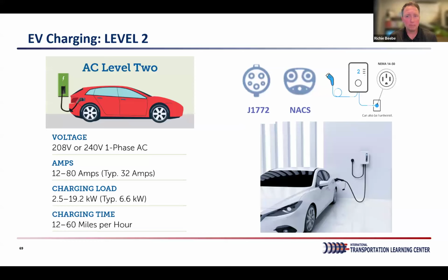So level 2 charging, you'll see this at residential facilities. It's a little bit faster of a charge. You can get anywhere from 12 amps to 80 amps, but typically what we see is a 32 amp load on these units, and that's due to the battery management system on the EV vehicle. It can only handle up to, some of the vehicles out there, 11.1 kW is what we see. So understanding what the vehicle can accept and what the charger can output is definitely key, because even if you bought an 80 amp charger and spent extra money on it, your vehicle most likely won't be able to accept that charge rate.